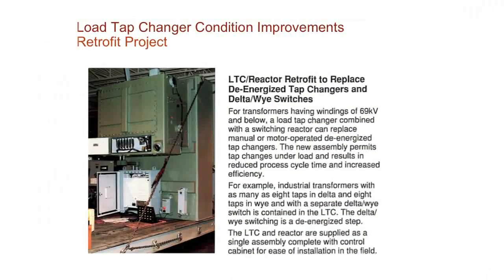In this particular case, we had to put a throat on the LTC. The new LTC coming in was actually larger. I say larger, it was wider than the old LTC, so we had to build a throat to bring the transformer tank out wider. Had to push the window footprint of the transformer out a little bit, but we're able to do those things if we have the information.